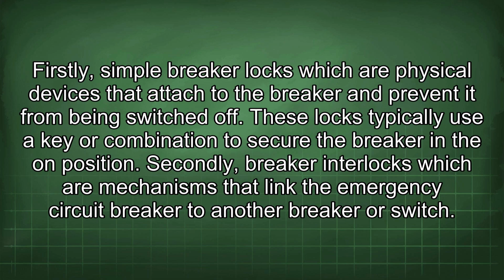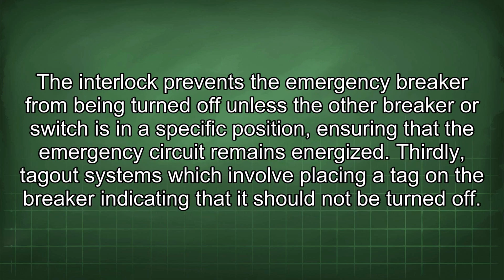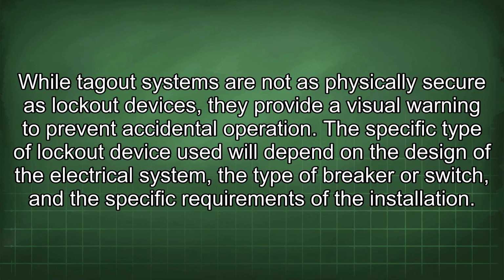Secondly, breaker interlocks, which are mechanisms that link the emergency circuit breaker to another breaker or switch. The interlock prevents the emergency breaker from being turned off unless the other breaker or switch is in a specific position, ensuring that the emergency circuit remains energized. Thirdly, tagout systems, which involve placing a tag on the breaker indicating that it should not be turned off. While tagout systems are not as physically secure as lockout devices, they provide a visual warning to prevent accidental operation.